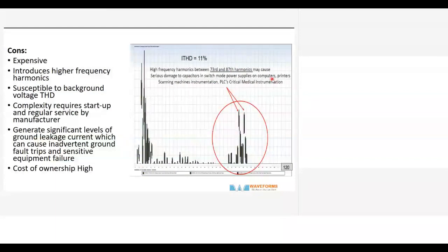Normally you have to use detuned power factor panels along with them, so that adds to your cost. The cost of ownership is very high. Besides the capital cost of buying it, the maintenance cost, service and all that can be very expensive. The failure of a PCB can be quite expensive, and it takes time. Normally, it has to be a trained service engineer to repair it. So that's the issue for industry. They can't afford failure. If one active filter fails, the entire plant comes to a grinding halt.